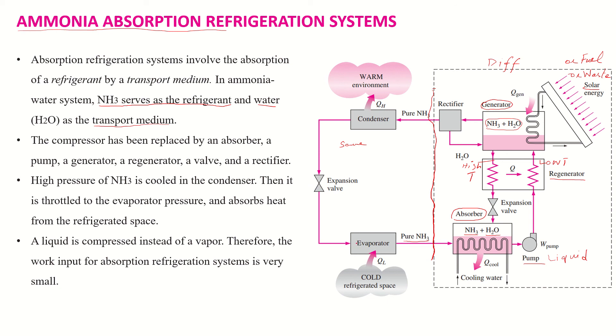After passing through the expansion valve, the ammonia vapor and liquid mixture is passed through the evaporator. In the evaporator, heat is absorbed from the refrigerated space and cooling is produced. After passing through the evaporator, the ammonia is completely converted into vapor form, and the cycle starts again from the absorber.